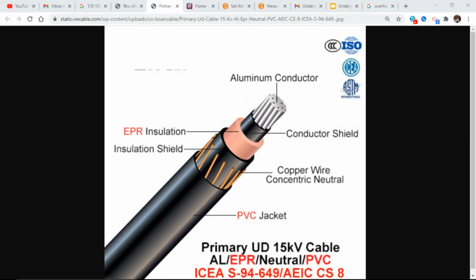I just went into Google and typed in underground primary cable, and there are many different pictures for it, but a lot of them come up with the actual parts of the underground primary cable. We'll discuss these real quick. Of course, there's the center conductor. That's the aluminum conductor in the core in the middle. The conductor shield really goes around the middle core area, one, to keep it compact, and two, as another shield area so it doesn't get punctured.